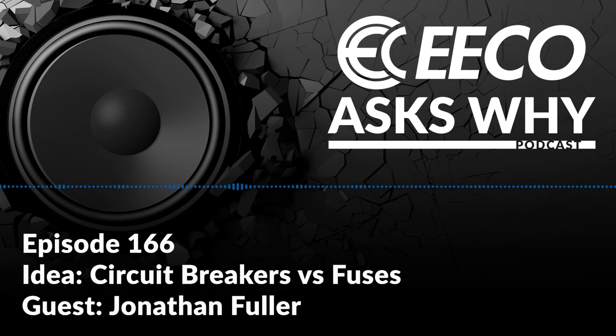But then I've also seen some customers that actually label on their machines, they'll label use 5-amp RK5 fuse only in this circuit. So they actually, with the label maker, just put a label right there where that fuse goes in that circuit and say, make sure you're using only this type so that there's no confusion of, hey, what kind of fuse do I need? What amperage is it? Just because, like you said, this is the fuse that was in that circuit, there's no telling if the person before you put something in there that was wrong. So it's always great to go back and reference that drawing or have it labeled clearly right there so that everybody can see this is undeniably what's supposed to be here.